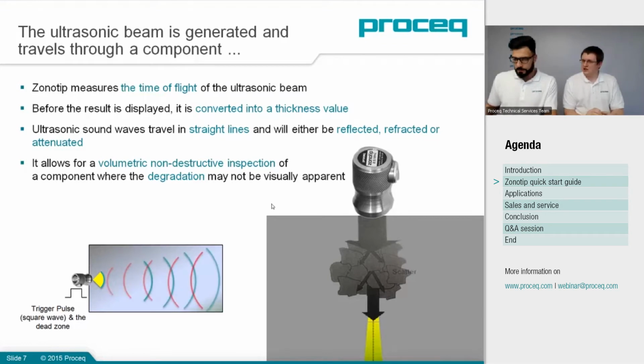Ultrasound travels in straight lines, and it will be either reflected, which is shown in the diagram on the left below, refracted, which is not really the case in thickness gauges but other devices, or attenuated, which is shown on the right below, and that depends on the material properties. What you also get with a single crystal is what we term a dead zone, and that's where the probe is ringing from the transmit pulse and it's not ready yet to receive any signal.